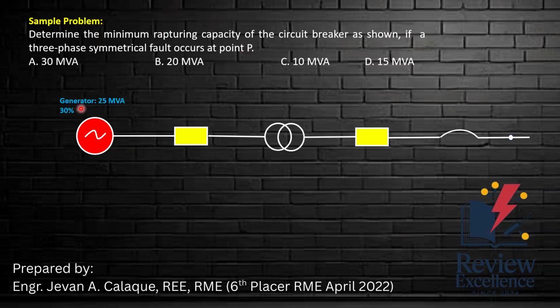So we have our generator, which is 25 MVA and 30% per unit. This is our first transmission line or the primary transmission line, to which yung rating niya is 10 MVA at 15%. Next is our transformer, 20 MVA at 20%, to which yung kanyang turns ratio is Y delta 10:1. Next is our secondary transmission line, which is also equal to 10 MVA and 15%. This is our circuit breaker, and this is the point to which the three-phase symmetrical fault occurs.